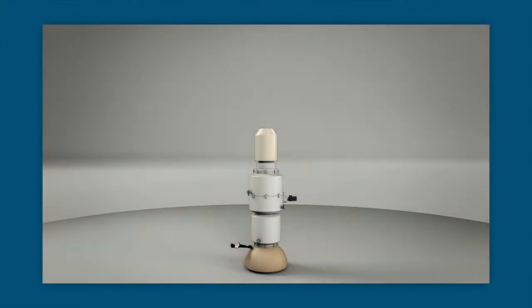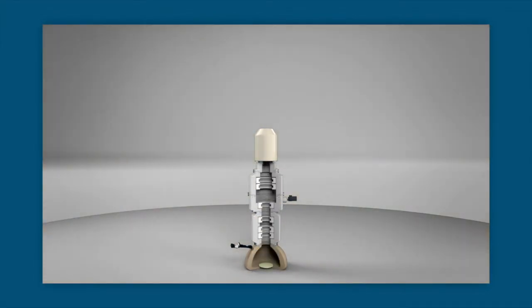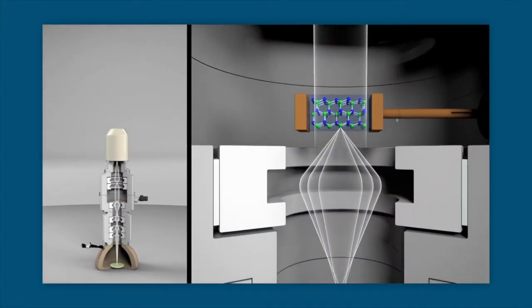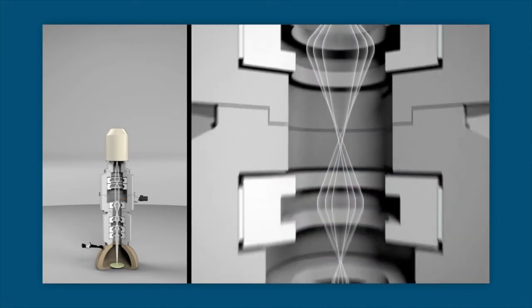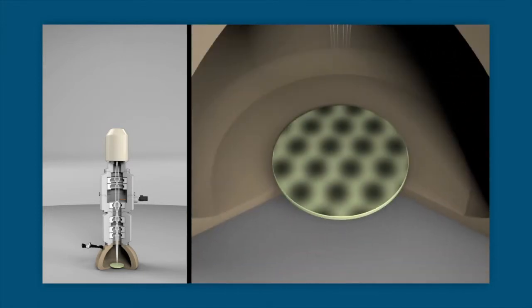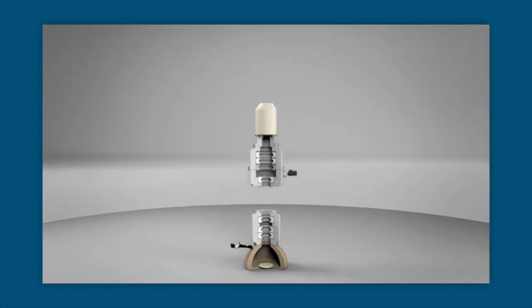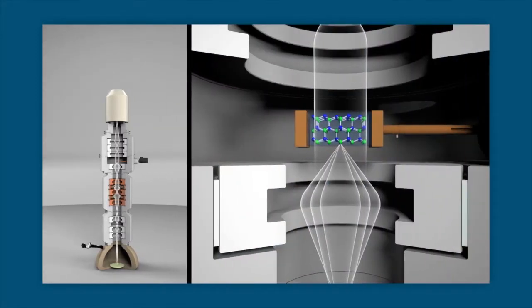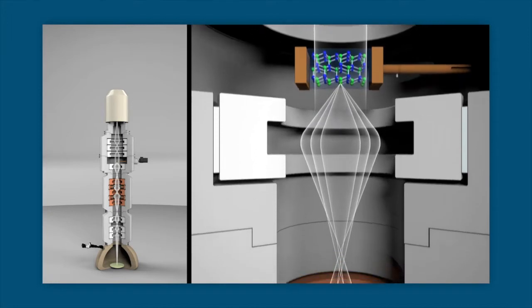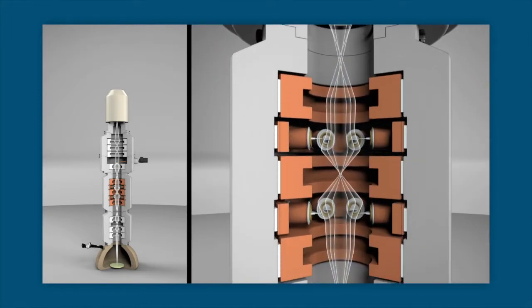If we look back to the types of electron microscopes used in perhaps the 1990s, these microscopes suffered from both of these deficiencies. Spherical aberration and chromatic aberration limited the resolution so that structures were often not imaged with truly atomic spatial resolution. It was only in the late 1990s, with the advent of spherical aberration correction as a result of the collaboration between Rose, Haider, and Urban, that new hardware allowed spherical aberration to be corrected.